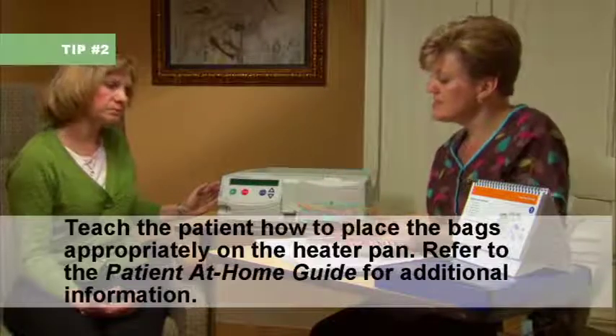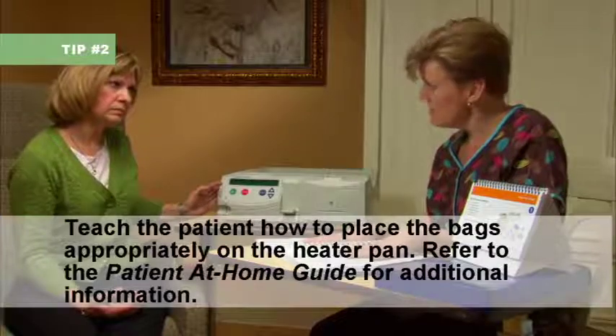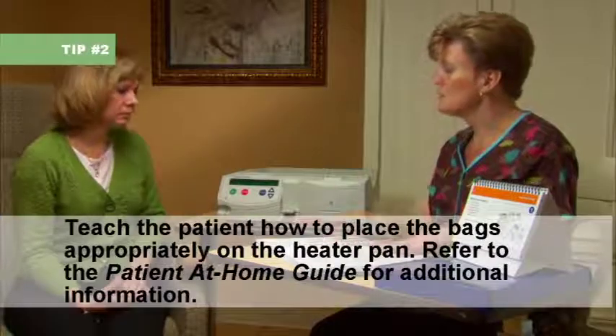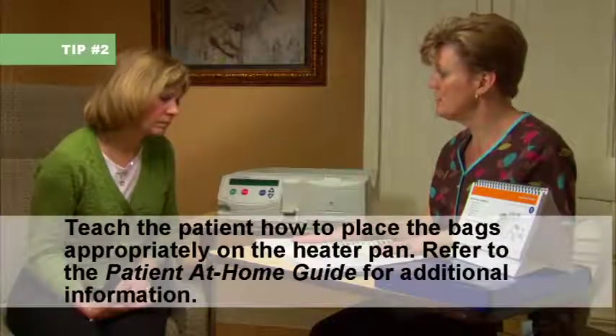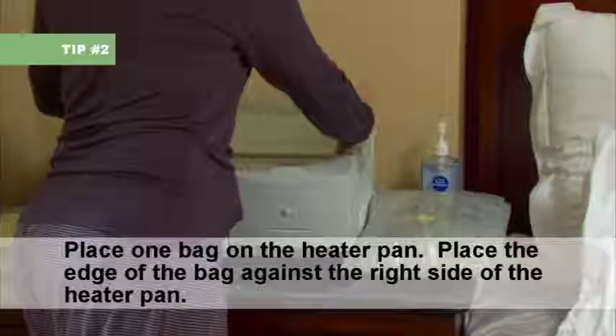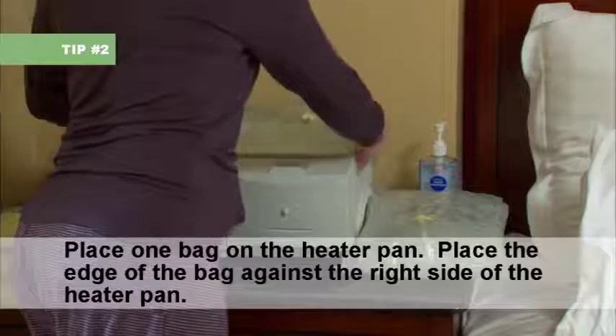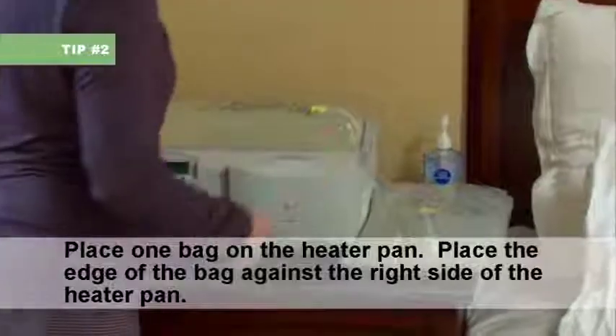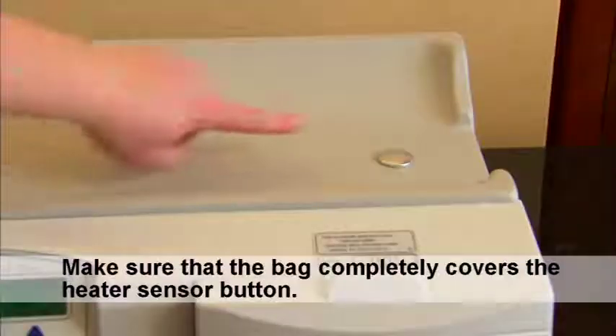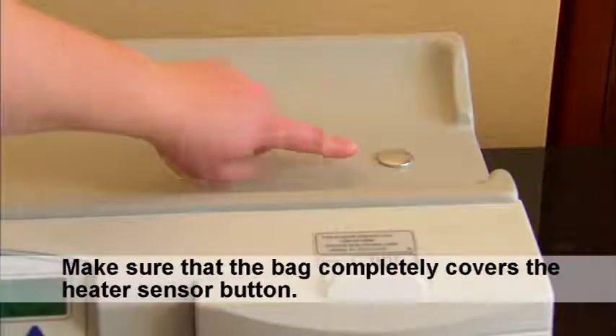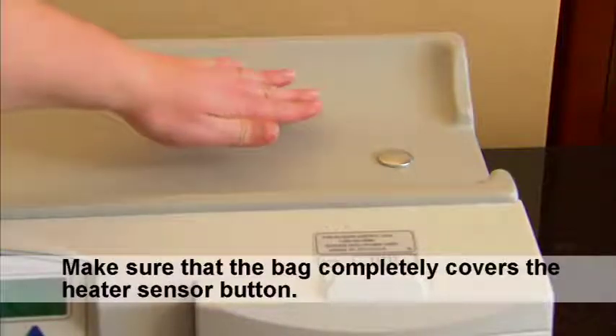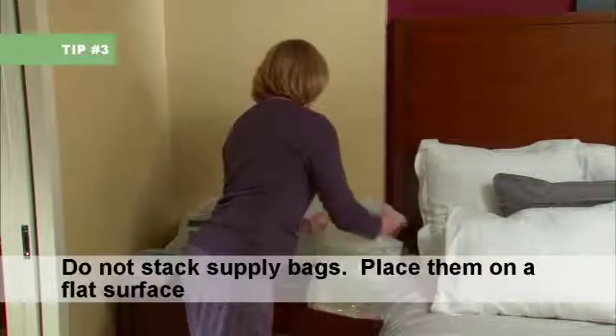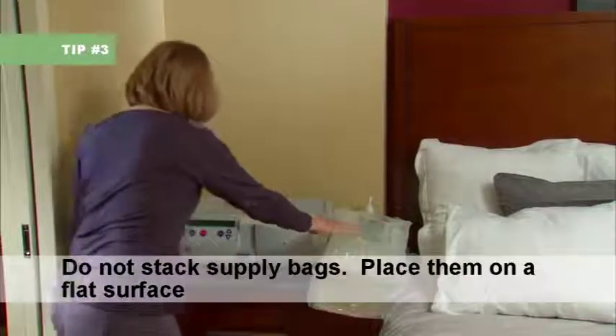Tip number 2. Teach the patient how to place the bags appropriately on the heater pan. Refer to the Patient at Home Guide for additional information. Place one bag on the heater pan. Place the edge of the bag against the right side of the heater pan. Make sure that the bag completely covers the heater sensor button. Tip number 3. Do not stack supply bags. Place them on a flat surface.